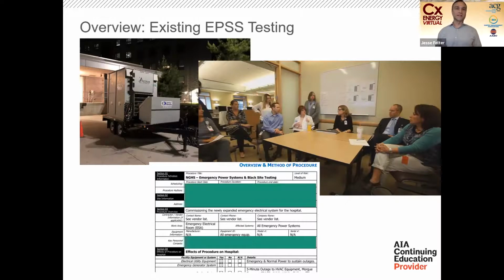Even the head nurse, sit down. What does this test look like? The concern of, well, we don't want to cut power to the building. Well, what if we can start the generators, transition load—whether it's open or closed transition—and minimize impact or any perceivable difference to priority one loads, then relegate the test to demonstrating shedding of new and/or existing non-priority one devices.